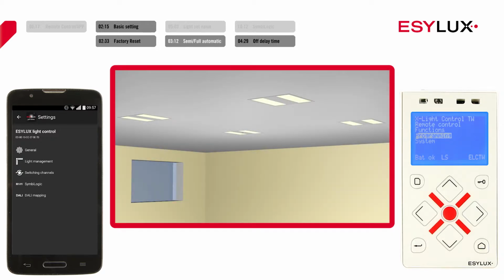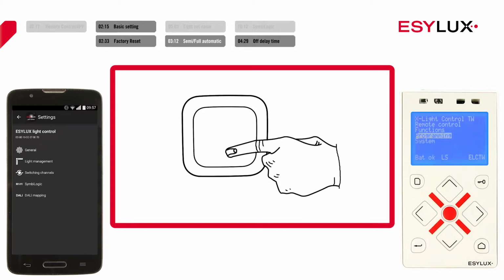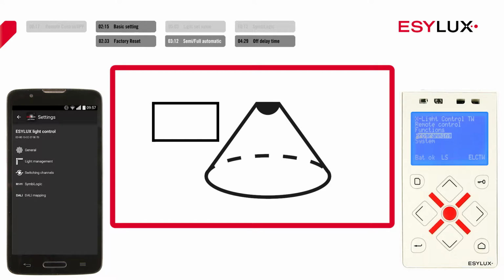You can choose between semi-automatic and fully automatic mode. In semi-automatic mode, the light only turns on when the button is pressed. In fully automatic mode, the light also switches on if the presence detector has detected a movement and the ambient light is below the preset light target value. The process for setting the light target value will be explained later.